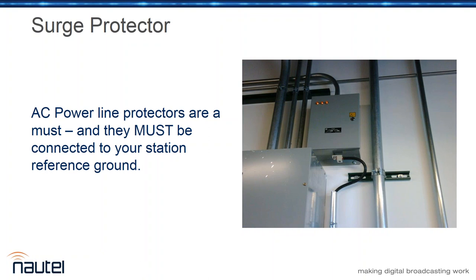If it's an MOV, for sure it's a bidirectional device. So if you get a spike on the tower, a tower strike, and ground potential spikes high, it can clamp through the surge protectors, through the MOVs, and dissipate out on the millions of miles of AC wiring that the power company provides and on all their grounds. So absolutely have a surge protector, have it connected to your reference ground, and make sure it's connected to the AC lines with the shortest possible run.